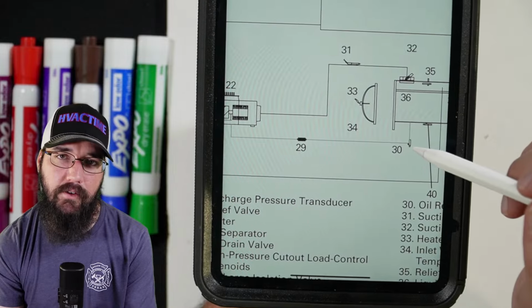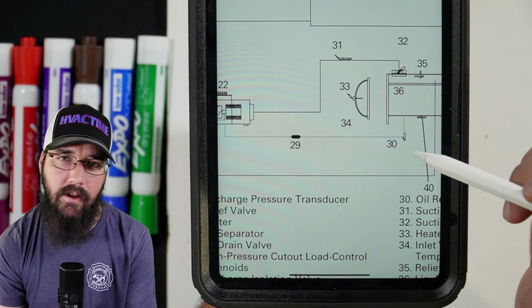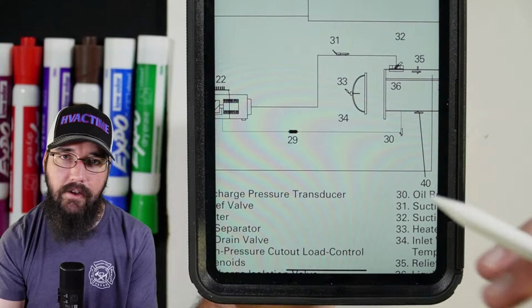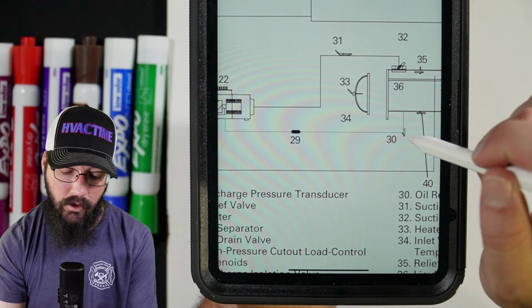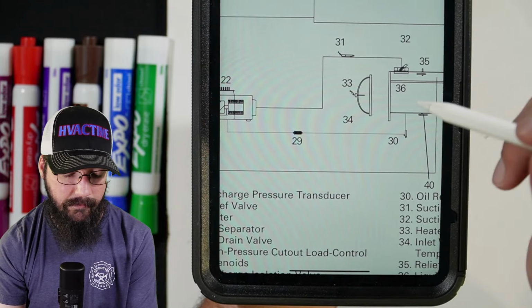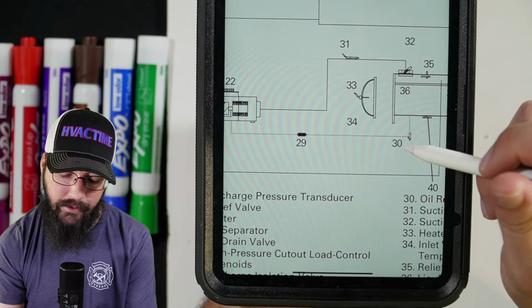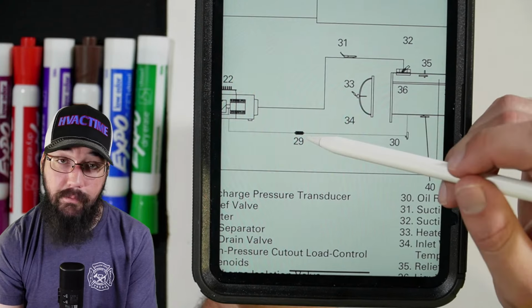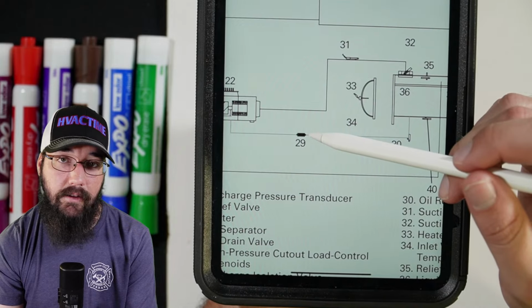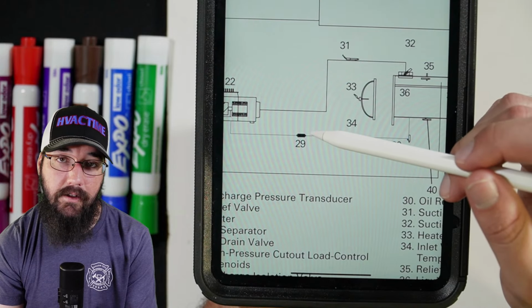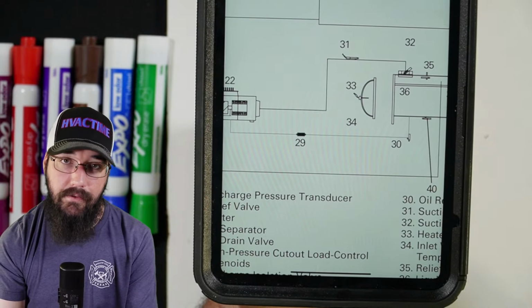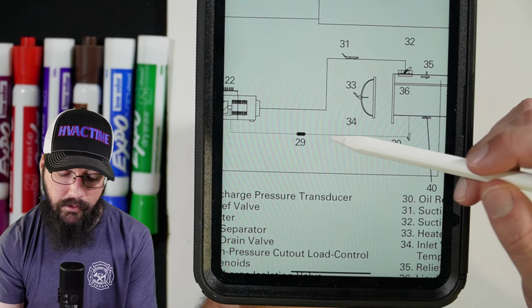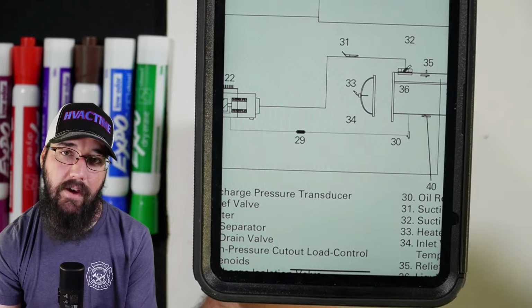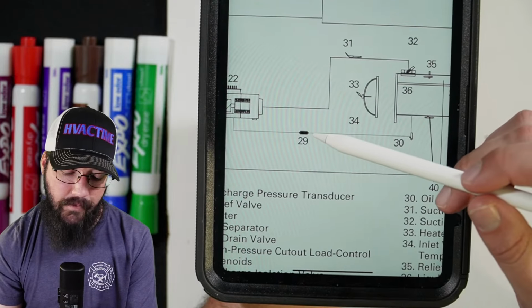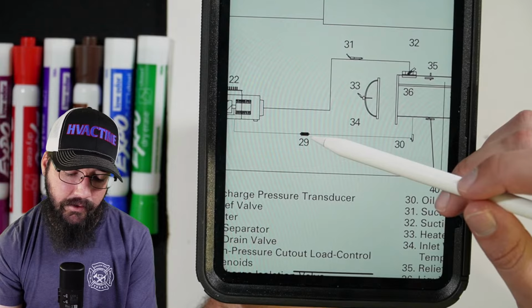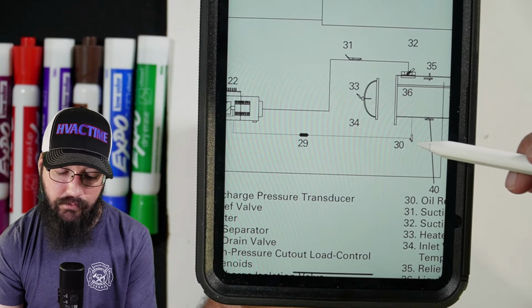I don't remember if these RTACs require that or not. I know that on a Trane CVH, their big centrifugals, you are required to do that in the field manually. Anyway, this valve could be one issue. Another issue could be this dryer. If this dryer has gotten plugged up and is not allowing flow through it, that's also going to cause the oil to begin to stack in the evaporator in the wrong way. So that would be something else I'd want to pay attention to: is it a dryer issue? Is this valve having an issue?